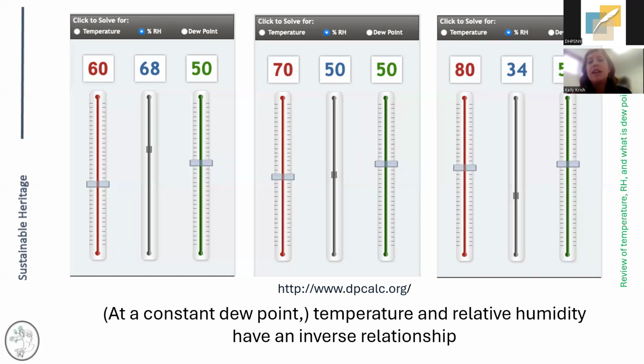And then as we increase that temperature on up to 80, you can see how the relative humidity is starting to come down. So you can use this resource to kind of play around and see with specific numbers how your dew point is locked in, how you can change the temperature and RH, and which combinations are possible. So not every combination is possible at specific dew points. So it's just another way to visualize this.